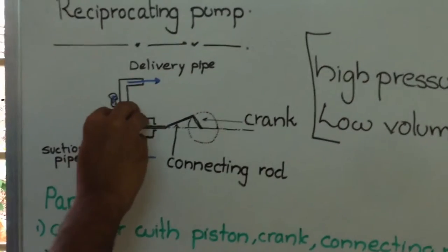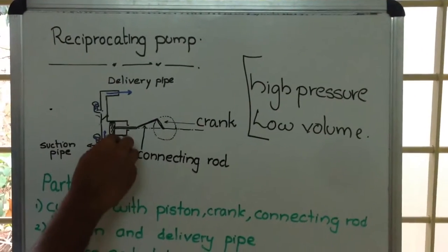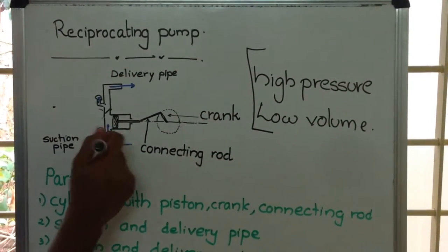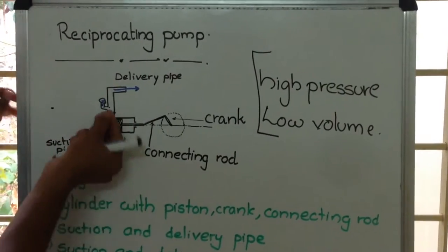As the piston moves to the right side, a partial vacuum is created inside the cylinder. At the suction, atmospheric pressure is present. Since this atmospheric pressure is greater than the partial vacuum inside the cylinder, it pushes water through the suction pipe into the cylinder.